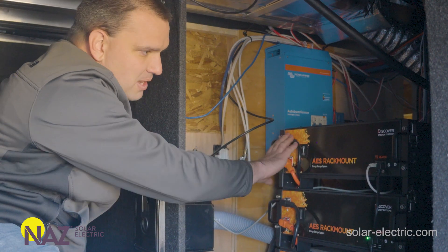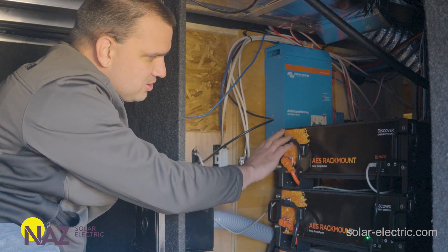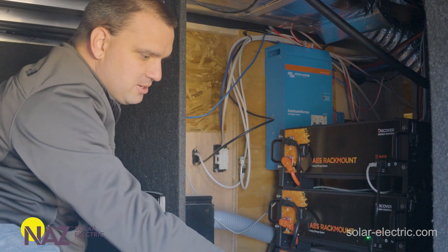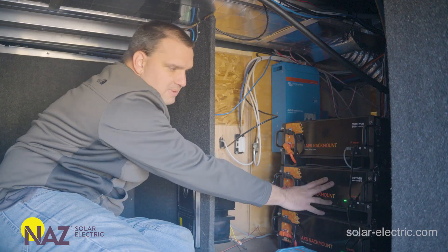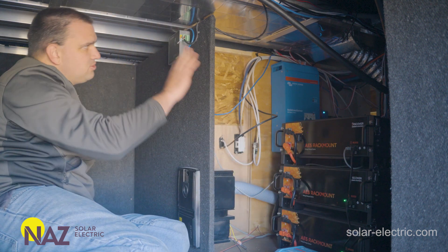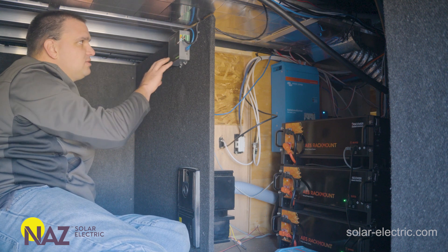Each of these batteries has a positive and negative using an Amphenol Radlock connector. Each of them has their own battery cables coming to the Lynx Power In, paralleling them all before they go to the Victron system. All these batteries have a little communication cable paralleling the communication, which then goes to the Lynx 2 right here. This Lynx 2 is giving us closed-loop communication to Victron.